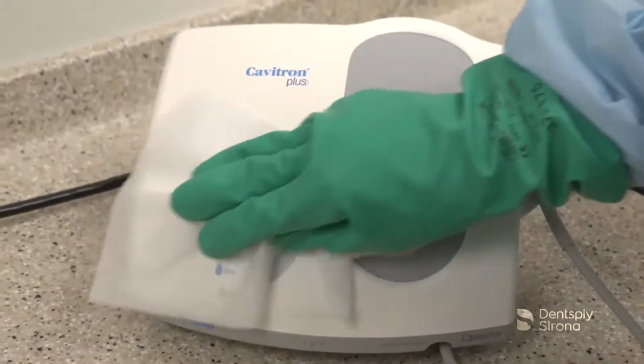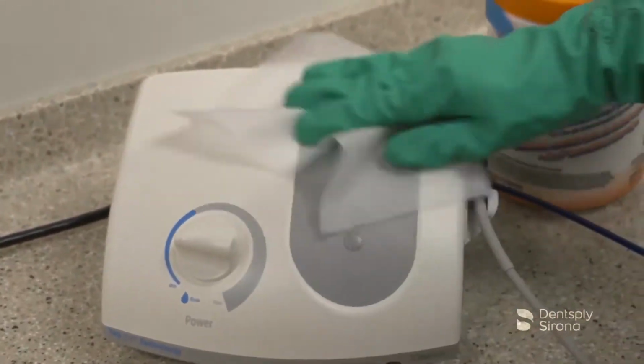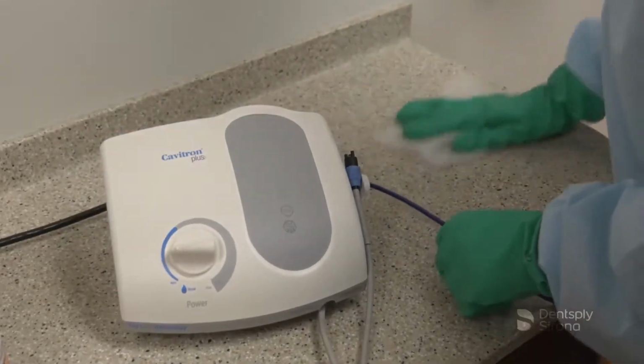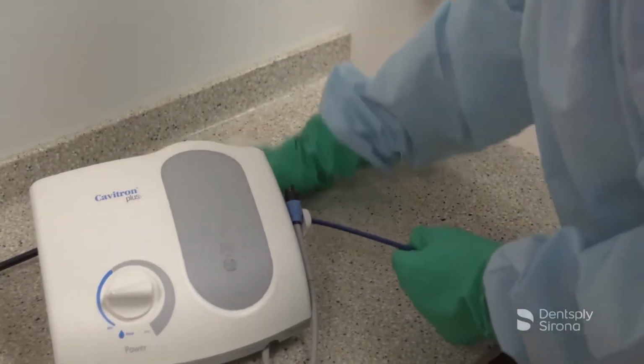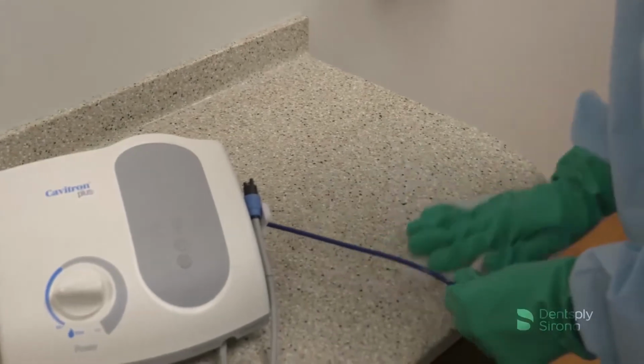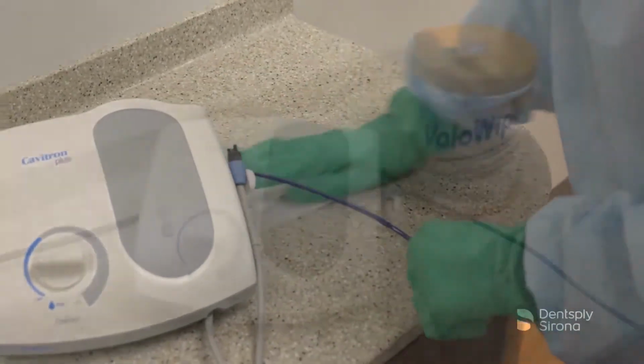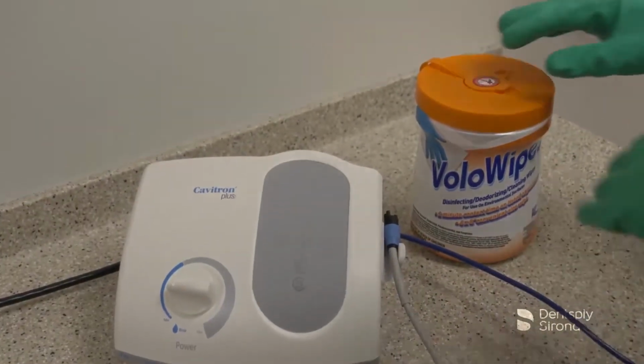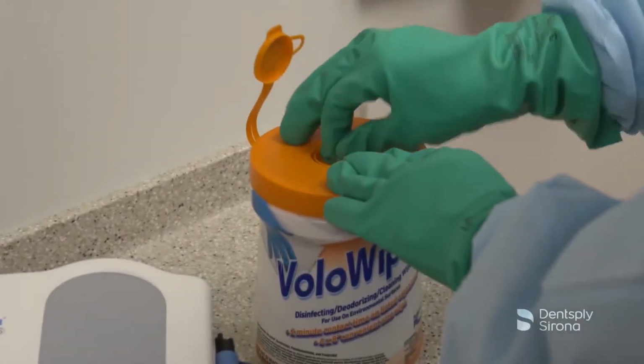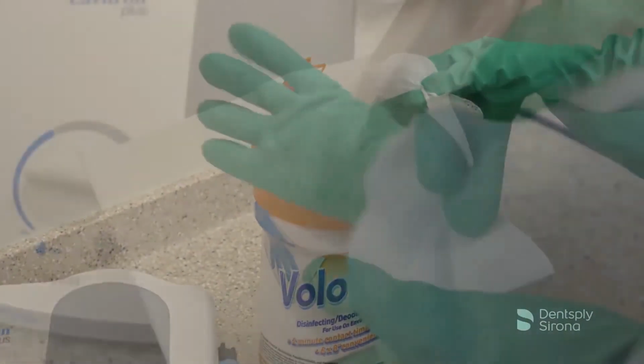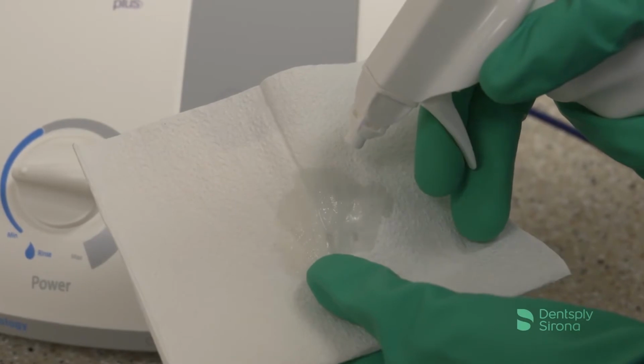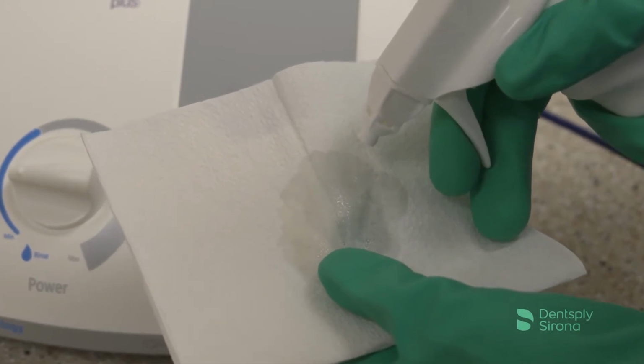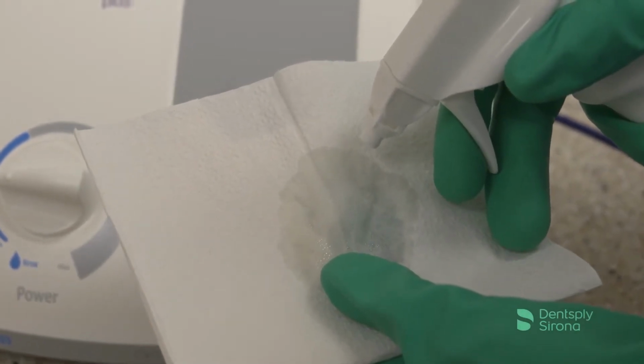A two-step cleaning process is recommended when visible soil and debris are present on environmental surfaces. The soil and debris must be cleaned prior to disinfecting the surface with a disinfectant wipe or spray. To prepare the unit for the next treatment session, utilize a disinfectant wipe or generously spray disinfectant solution on a clean cloth. Do not spray disinfectant solution directly on the system surfaces.